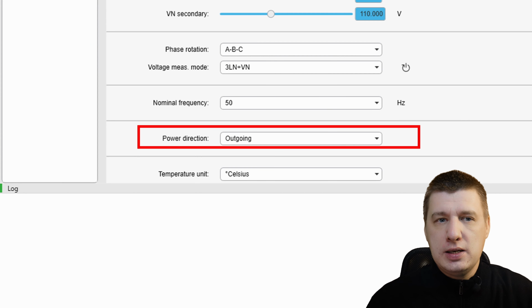When you are configuring the scaling for your P5, there is a setting that determines how your relay reads the flow of energy: power direction. If you get this wrong, your active power reading will be negative when it should be positive, and your direction protection could fail to operate during a fault. In setup, you find this under general and scaling. There is a drop-down menu, power direction, where you must choose between two options, outgoing or incoming. This selection tells the relay which way the positive current is supposed to be flowing.